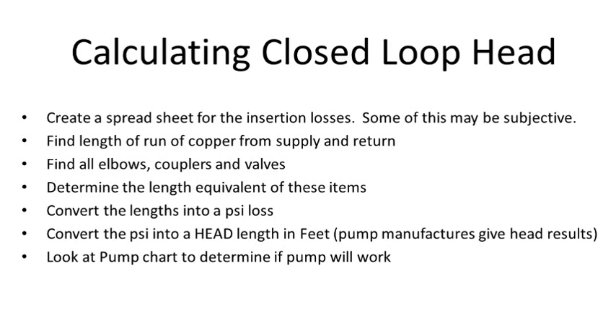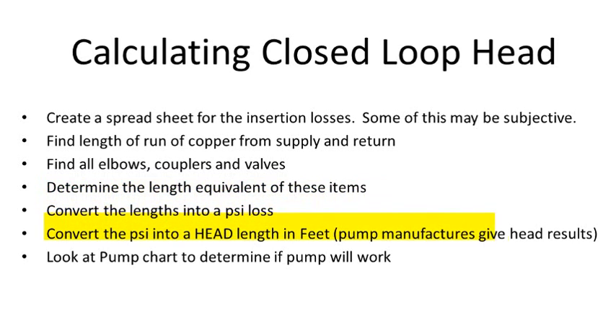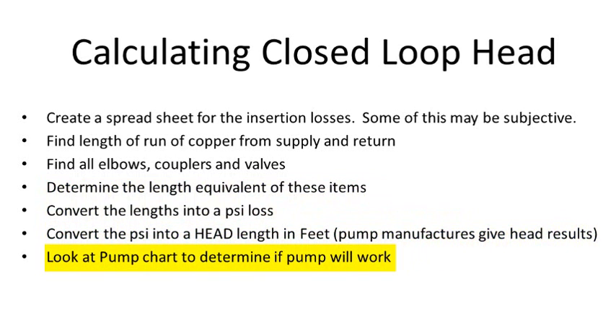We need to make a very good value judgment for the length of copper on the run to the supply and to the return. We need to count all the valves, couplers, elbows, pumps, and anything else in the system that will create loss, then convert that into an equivalent distance. Once we know that length, we convert it to a PSI loss. Pump manufacturers give results in feet of head, so we'll convert our PSI into a head distance, then look at a chart to determine if that pump meets the criteria.